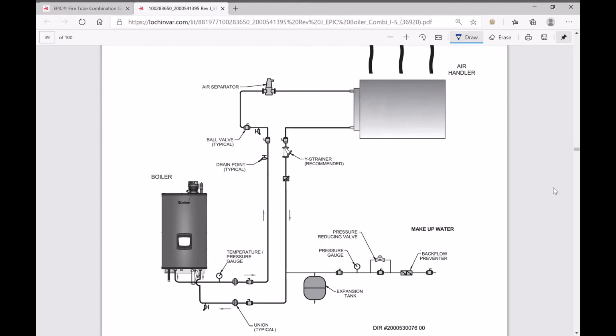So this is the Epic boiler manual. It encompasses the boiler as well as the combi. And what we're looking at here is an Epic boiler with an air handler, and it's piped directly into that air handler without closely spaced tees. So typically in the last 20 or so years, we've seen closely spaced tees here, and we've seen a pump coming back to the boiler.